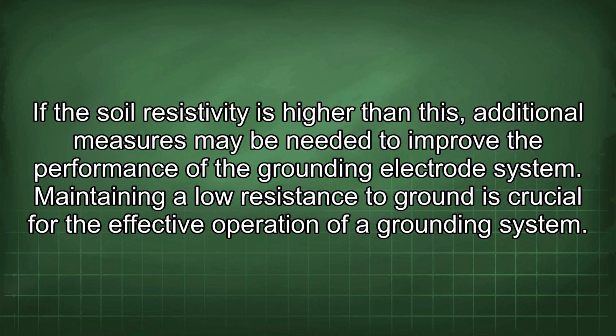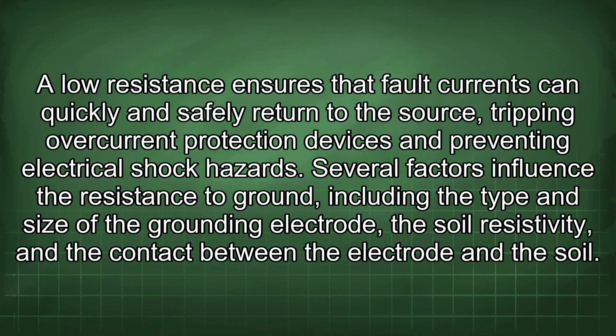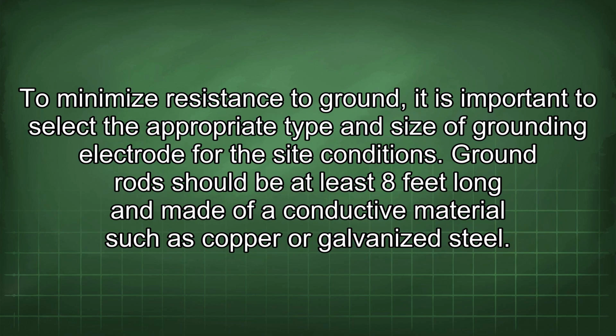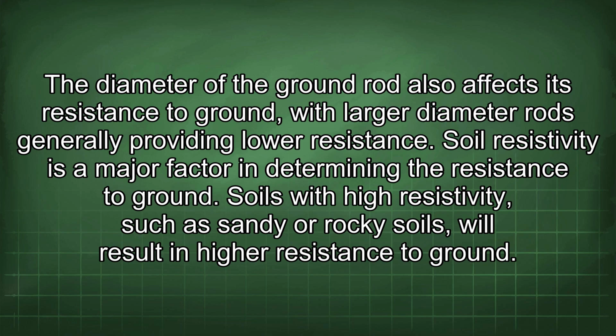electrode system. Maintaining a low resistance to ground is crucial for the effective operation of a grounding system. A low resistance ensures that fault currents can quickly and safely return to the source, tripping overcurrent protection devices and preventing electrical shock hazards. Several factors influence the resistance to ground, including the type and size of the grounding electrode, the soil resistivity, and the contact between the electrode and the soil. To minimize resistance to ground, it is important to select the appropriate type and size of grounding electrode for the site conditions. Ground rods should be at least 8 feet long and made of a conductive material such as copper or galvanized steel. The diameter of the ground rod also affects its resistance to ground, with larger diameter rods generally providing lower resistance.